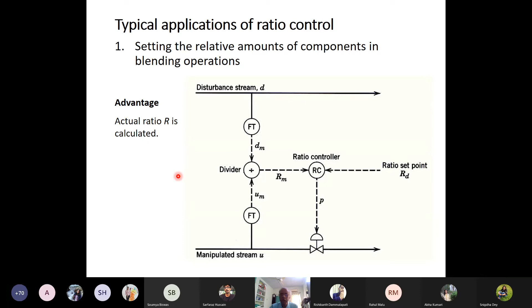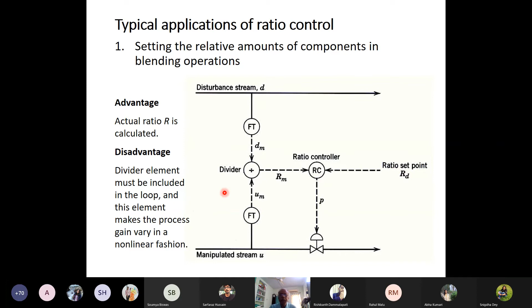But the disadvantage is that this divider element is in the feedback control loop. If you have the divider element in this feedback control loop, the loop becomes nonlinear. So here the ratio, let's say U by D, for a change in the disturbance, delta RM by delta D is a nonlinear term. So the change in the ratio with the disturbance is a nonlinear term, right? It will give minus U by D square. Since we are putting this divider element here, we are making this loop nonlinear. So that is the disadvantage. In this strategy, the divider element has to be included in this loop, which will make the process gain nonlinear.